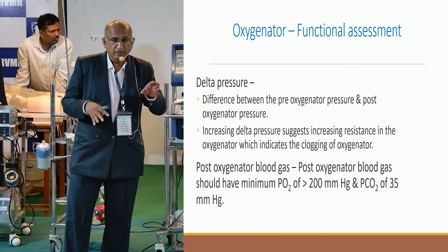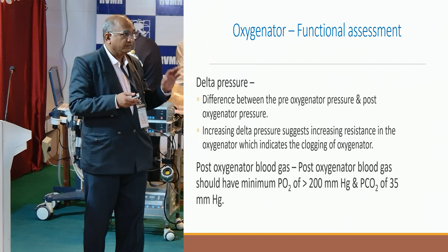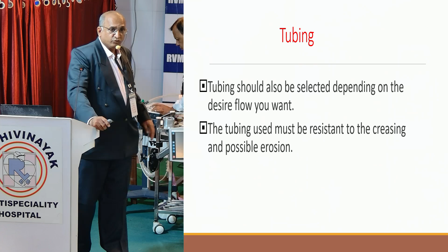That occurs only when the oxygenator is failing or getting clogged; you get a change in the delta pressure. Each and every oxygenator has a different delta pressure. Again, what is more important is the trend of the delta pressures.